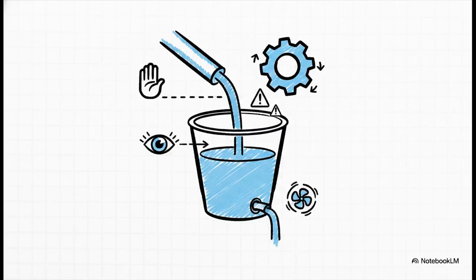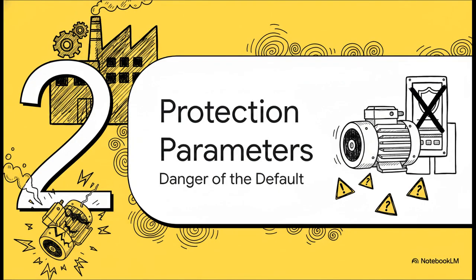For those of you who might be new to VFDs, it helps to think of your motor's thermal capacity kind of like a bucket. Pulling a heavy electrical load fills that bucket with water, which represents heat. Your motor's cooling fan? That's like a drain hole at the bottom. As long as you aren't filling the bucket faster than it can drain, you're golden. But if you overload the motor, the bucket fills up way faster than the fan can cool it. The I²T mathematical model is constantly watching the water level in that bucket. If it gets dangerously close to the top, it steps in, triggers an alarm, and stops the motor before it overflows and burns up.